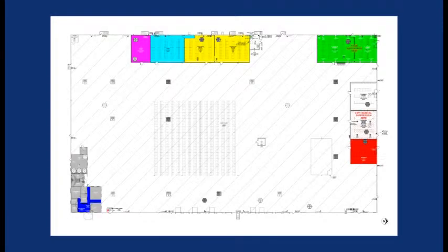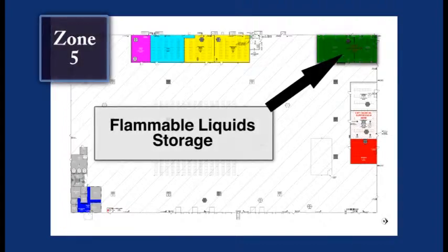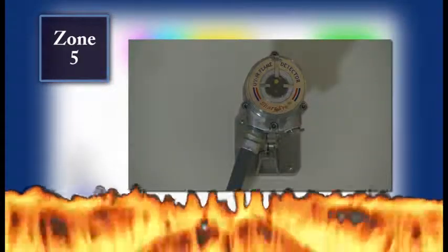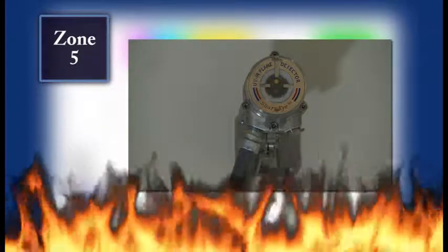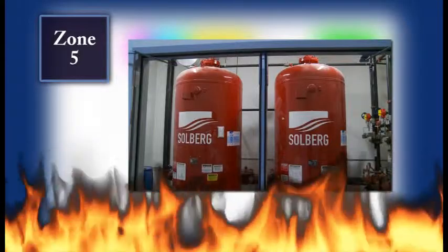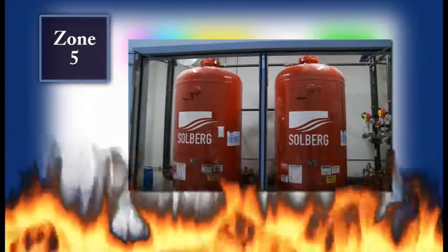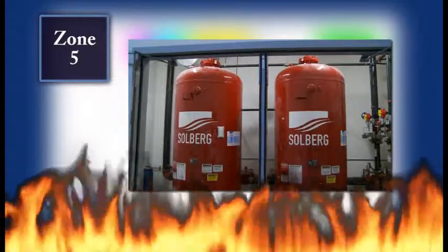The actual sequence of events in an alarm condition depends on where the event takes place. If the alarm condition is in the flammable liquid storage area, it will activate the AFFF-AR system. The likely sequence of events would be as follows. Failure of the heat sensing element will result in immediate system operation in the affected area. The AFFF-AR system will activate, resulting in the discharge of AFFF-AR solution through all the open foam water heads in the flammable liquids storage room.